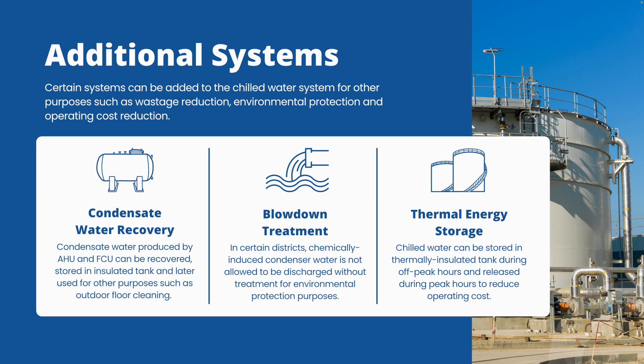The third additional system is thermal energy storage. This is a large insulated tank filled with glycol balls that can store a lot of energy. During off-peak hours — when electricity tariffs are lower — we run the chiller to charge up energy in the thermal energy storage tank. During peak hours, when electricity costs are higher, we stop or reduce chiller operation and release the stored energy from the tank instead. This reduces electricity and operating costs significantly.